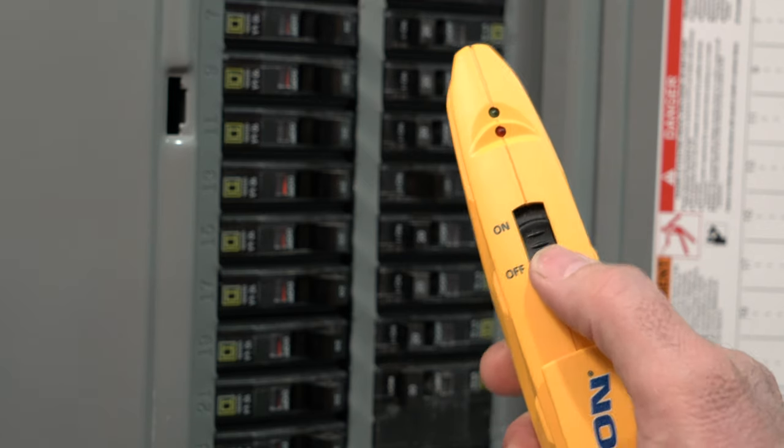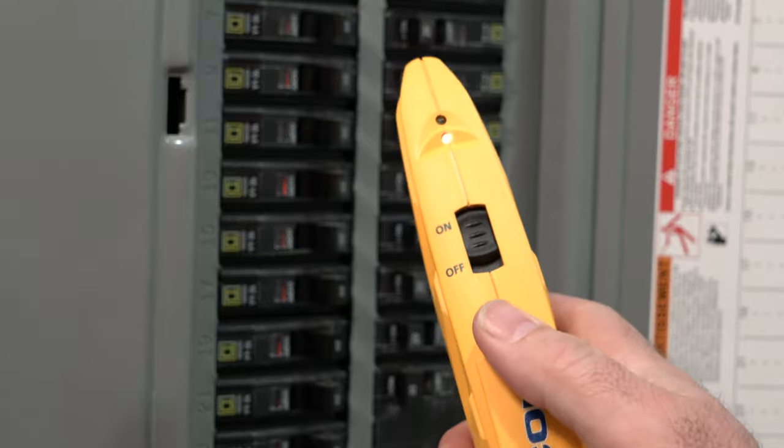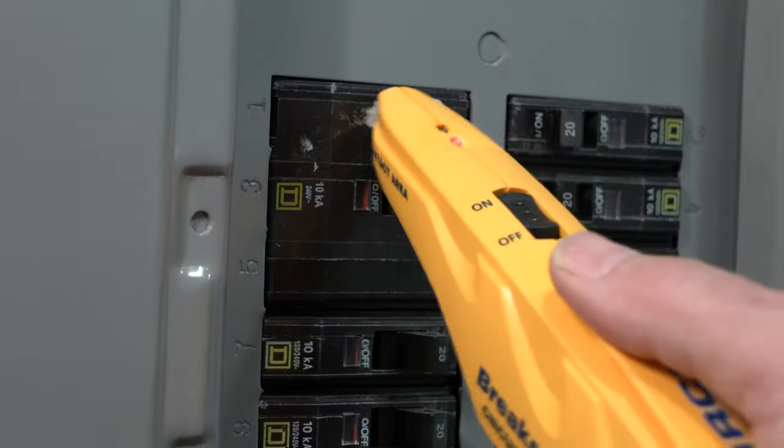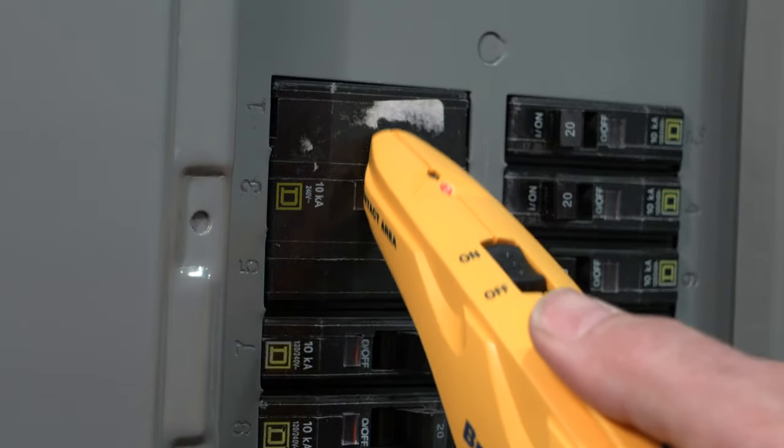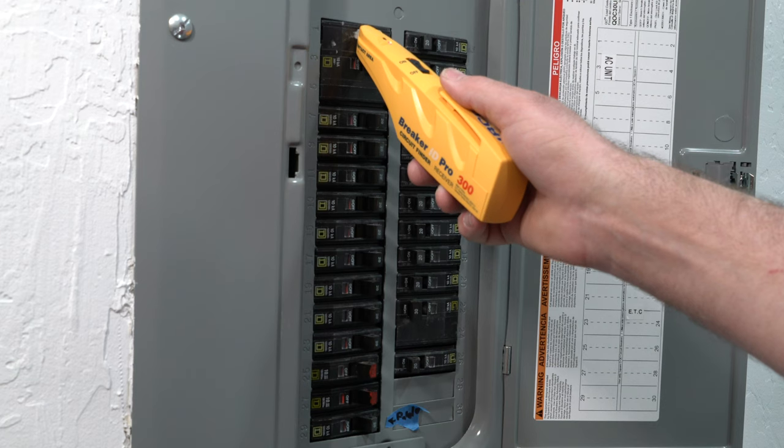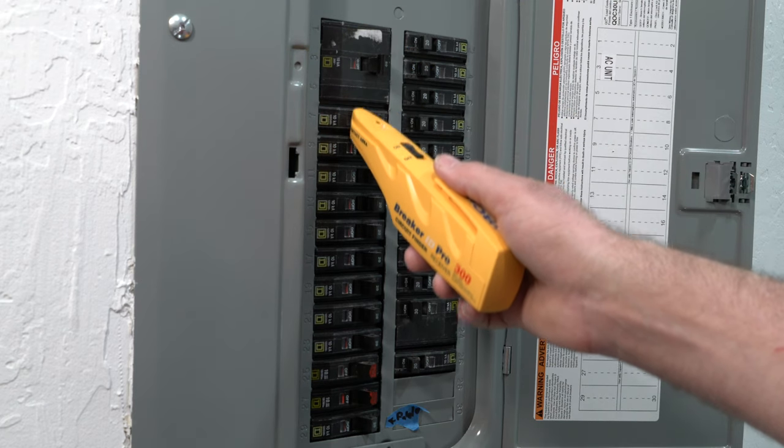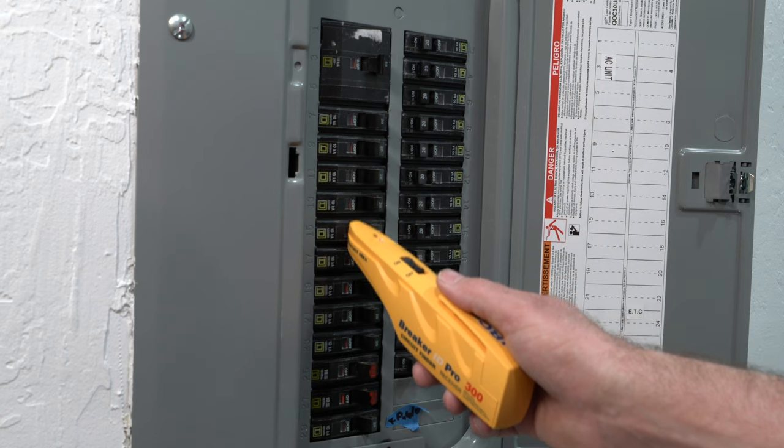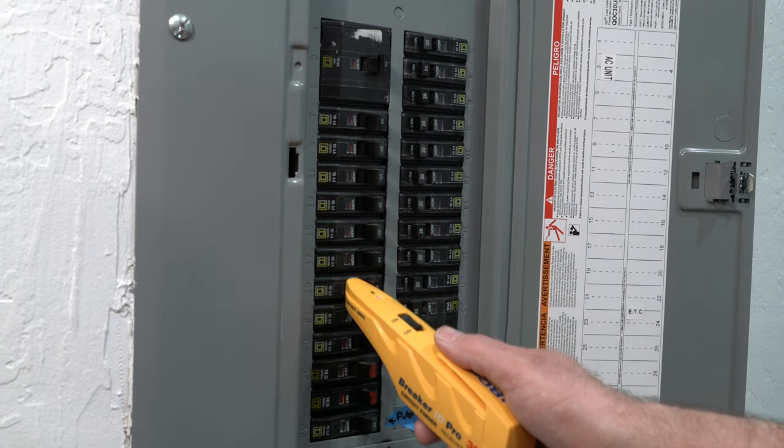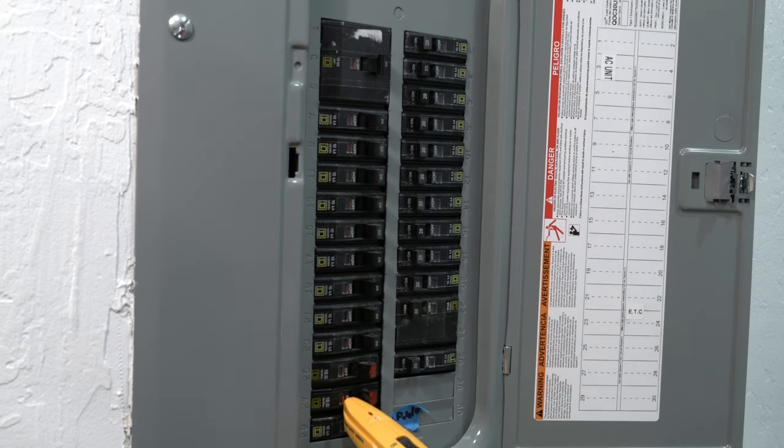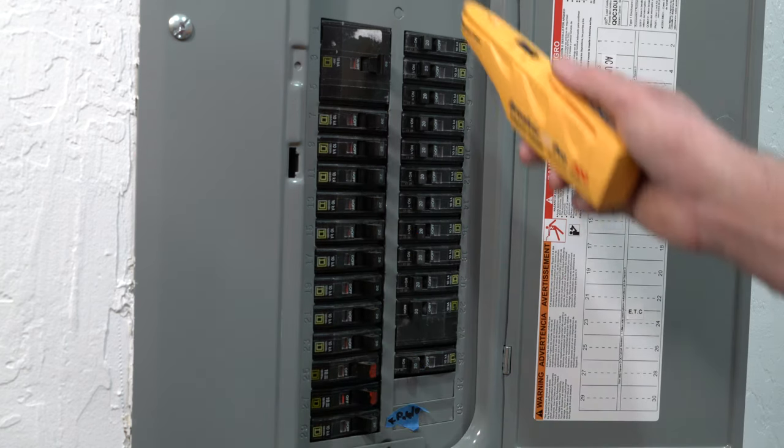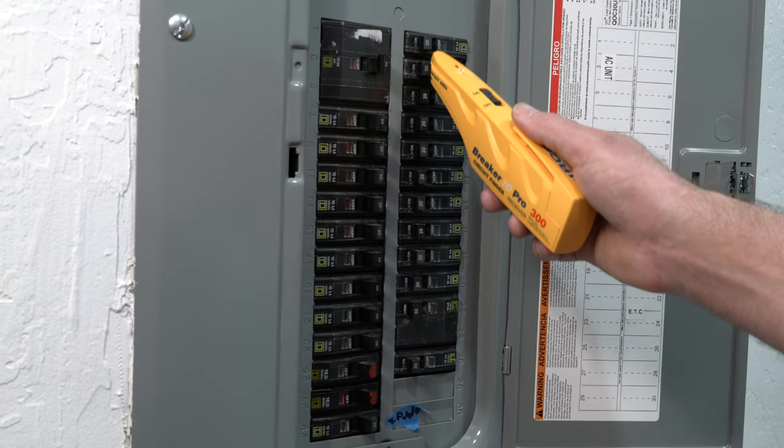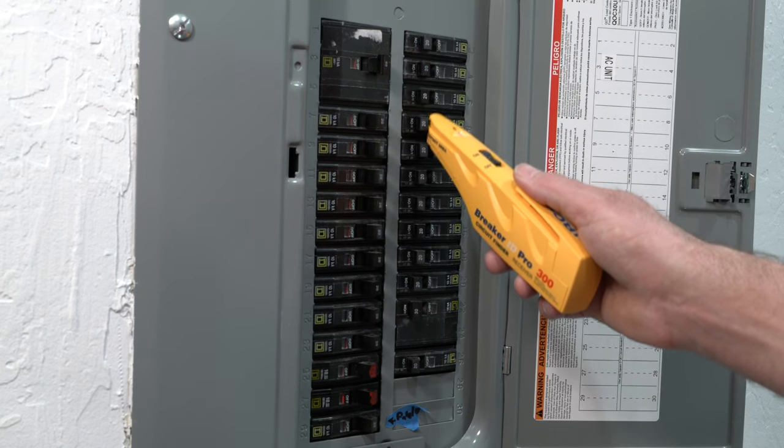At the circuit panel, switch the receiver to on, holding the receiver at an angle that gives maximum contact between the contact area and the breaker. Slowly scan over each circuit in the breaker box, making sure to touch each breaker during the scan without lifting the receiver nose away from the circuit breaker box.